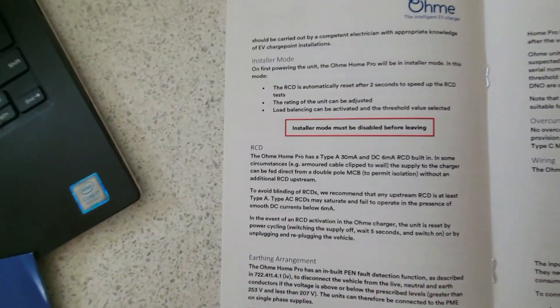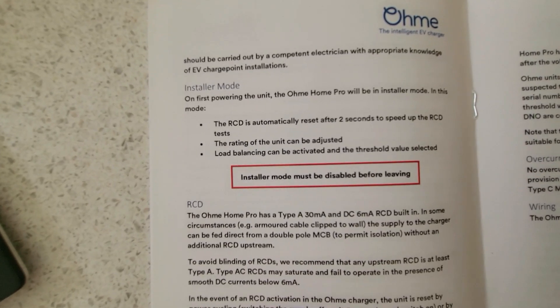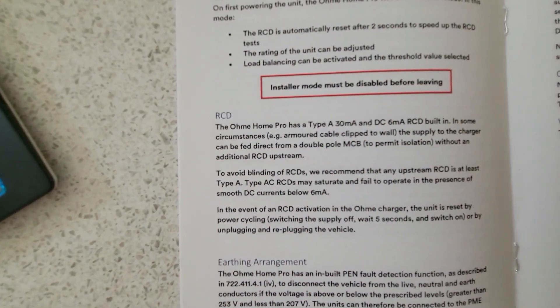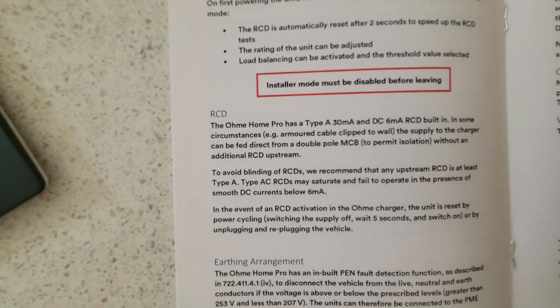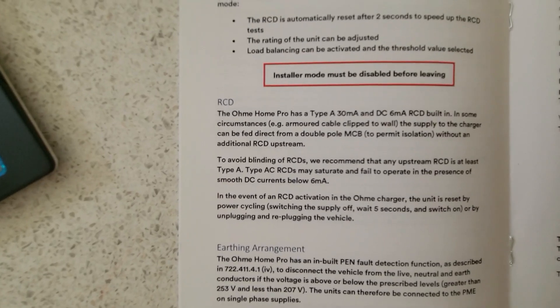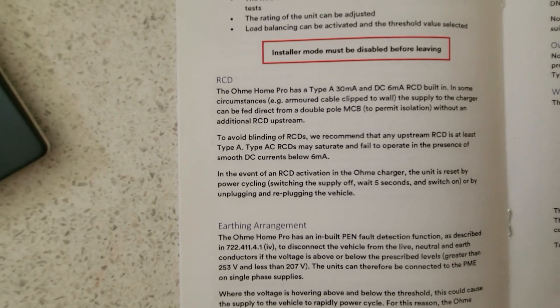On first powering up, it's in installer mode — the RCD resets after two seconds to speed up RCD testing, which is often a faff with other charge points. Ohme have thought about that — love it, makes our life easier. The manual notes that in some cases, if you're using an armoured cable clipped to a wall, the supply to the charger can be fed direct from a double-pole MCB to permit isolation. It also says to avoid blinding RCDs, any upstream RCD should be at least Type A.